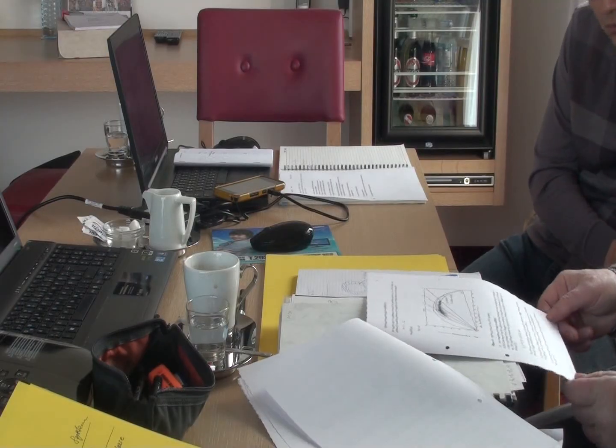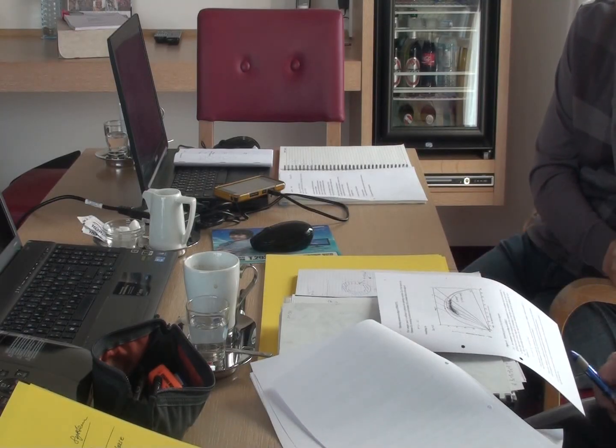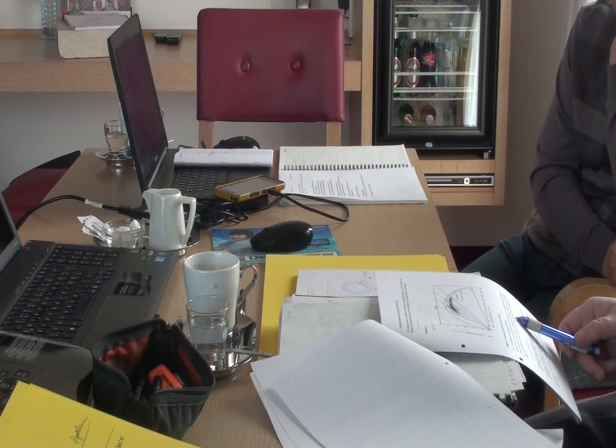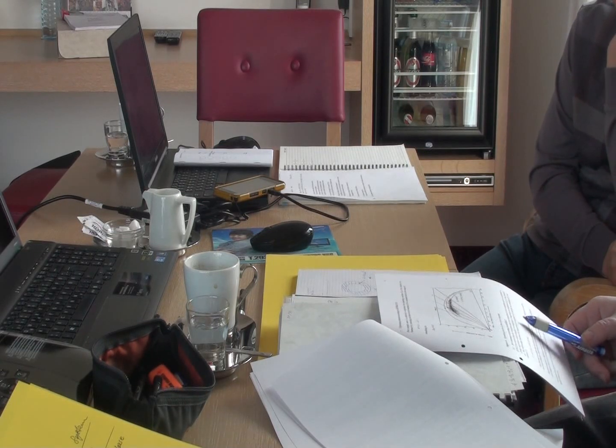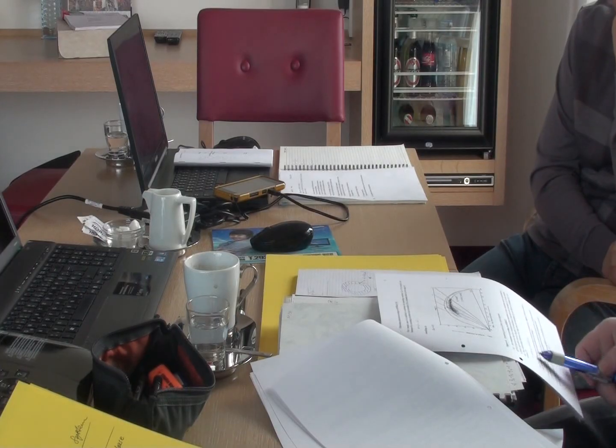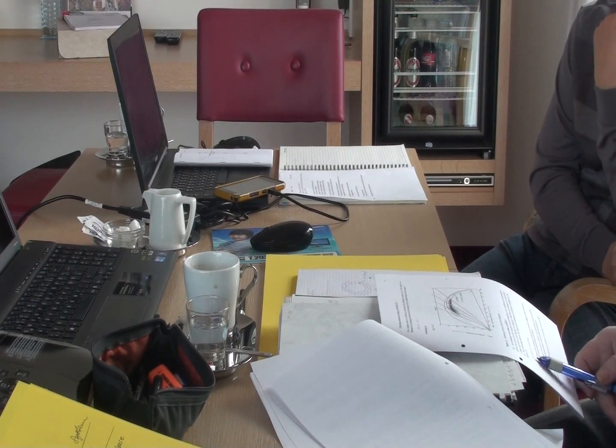There are some models to calculate the current, and one is given by Mr. Köhle. He says there's an additional arc reactance which can be given to the arc, and this is dependent on the arc resistance. The higher the arc resistance, the higher the additional arc reactance.